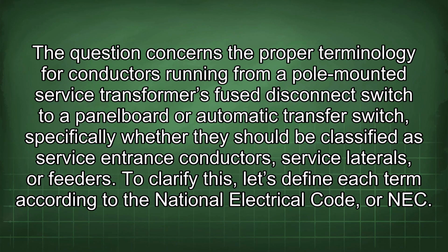The question concerns the proper terminology for conductors running from a pole-mounted service transformer's fuse disconnect switch to a panel board or automatic transfer switch, specifically whether they should be classified as service entrance conductors, service laterals, or feeders. To clarify this, let's define each term according to the National Electrical Code, or NEC.